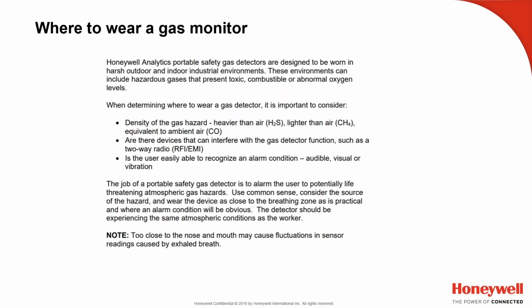In most of these confined spaces, the atmosphere is quite homogenized. If you do a pre-test prior to entry, oftentimes it'll be before you even open the hatch, and there might be some vent holes that you can drop the hose in, and you can do what's called an as found, or static, environment. That's more or less where the gases are going to stratify and hang out high, low, and equal to air based on their gravimetric weight. So the detector should experience the same atmospheric hazards once you go in.